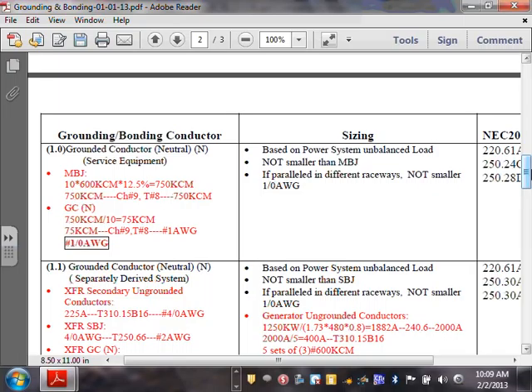Two options. Option number one, full neutral, fully sized. Engineers love that. We don't pay for copper, right? You guys are contractors. Every time you cut your copper is expensive. If you can get away with lower copper, and utilities tell you all the time, the neutral is not carrying a whole lot of amps at that level. So here is the minimum that you need to start. Always start with the minimum. The minimum by code that you size your neutral for your 200 amp panel or your 2,000 amp switchgear or your 4,000 amp switchgear, doesn't matter. The minimum that you go by, my friend, is based on the power system. First, the rule is if you know the unbalanced load, you size it based on the unbalanced load.